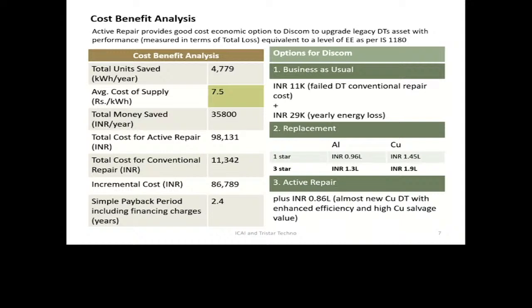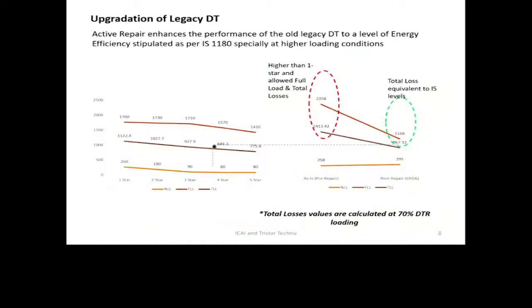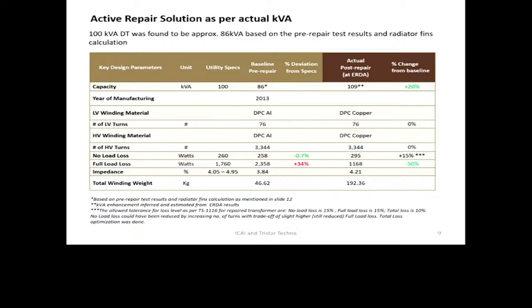Considering this, a cost benefit analysis was carried out, and it was found that the payback period would be around 2.4 years. In case of single star or 3-star, the replacement cost is also given by the active repair. At 0.86 lakhs, it's almost like a new copper distribution transformer, giving high efficiency and high copper salvage value.